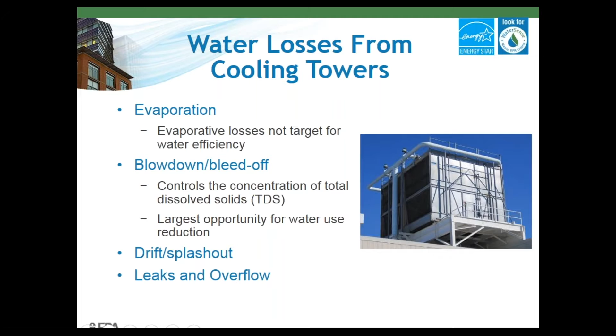One other way to do this is to coordinate with your water treatment vendor so you are able to maintain a high enough cycles of concentration, but not completely injure or hurt your cooling towers at the same time. To control your blowdown, it's typically used by a conductivity meter and a controller, and careful blowdown control will really offer the best opportunity for savings in the cooling tower system. You may also lose some water due to drift or splash out. And in a well-designed tower, this would actually be pretty minimal, but if you're noticing visible droplets exiting the tower, or every time you walk by the tower you get a little wet, you should probably spend some time and attention looking at your tower as well. Next slide.